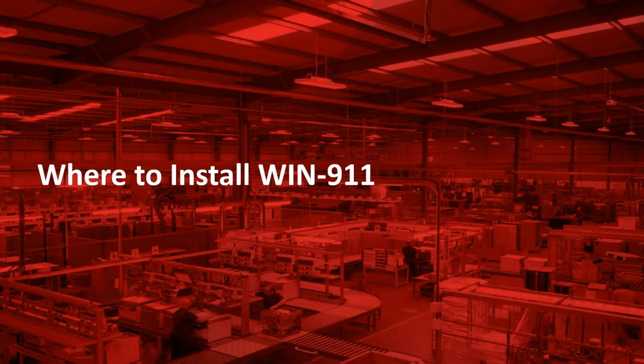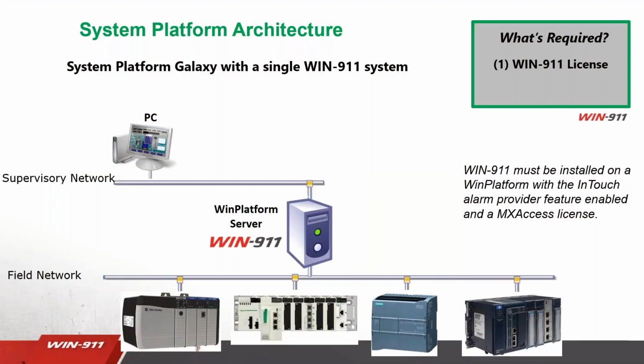So jumping right into where to install WIN-911 if you're using System Platform. The most important thing to know about this is WIN-911 must be installed on a WinPlatform that you can deploy with the InTouch alarm provider feature enabled and an MX Access license. So as long as it's on a WinPlatform that you can go out and deploy, that's where WIN-911 needs to be installed.